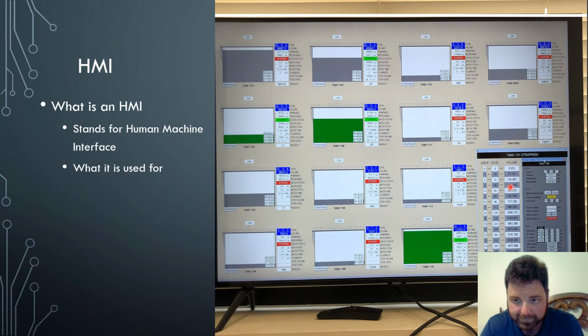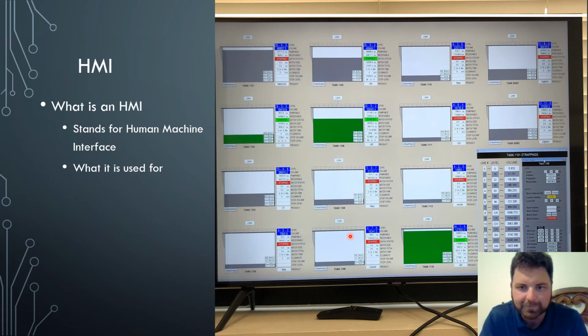The tanks have strappings, which means level, and level is referenced to volume. The level is not linear, so you actually have to have a strapping table to reflect the volume versus the level. That's how they base their batching, and that's how the PLC will know how much has actually come out of that tank. So these are pretty neat. And this is a pretty simple one. There are some machines out there that can do a lot of cool stuff, and this is how the operators are telling the machines what to do.